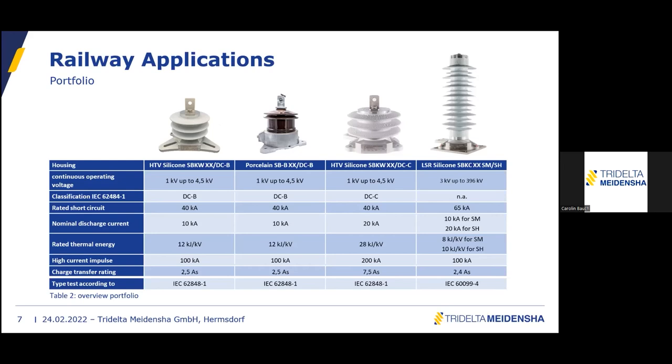Regarding development for speeds up to 380 km/h: for the SBKC, we are looking into a different shed design, still in development. For DC surge arrestors using HTV silicone, which has more stiffness, we are quite confident they work up to 380 km/h, but we have no test report yet. We are working with a customer to install it directly on a train, let it travel for weeks and months, and observe results with cameras. For now it is just an assumption based on experience.